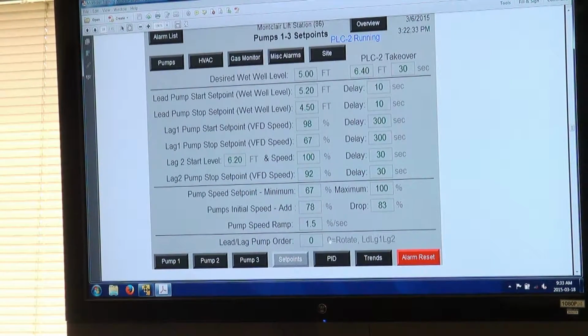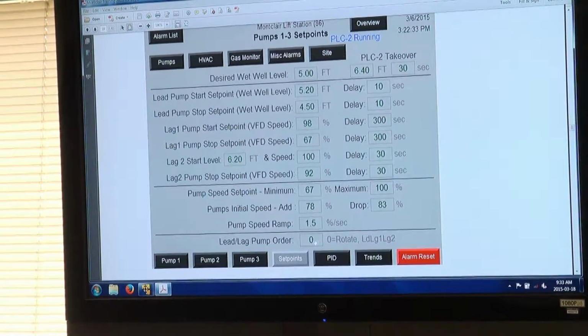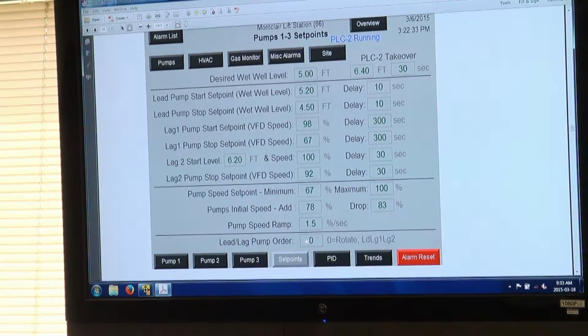And here's finally your order. If you were to put in a value of 123, that's going to mean your lead pump is 1, your second pump is 2, your third pump is 3. That's going to be a fixed order. It's not going to rotate. If you leave a 0 in here, then it's going to rotate. It's going to function like you guys are used to.